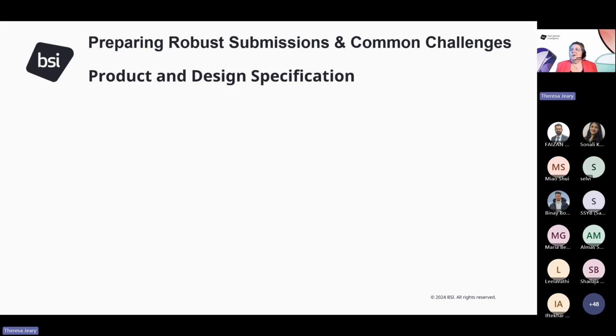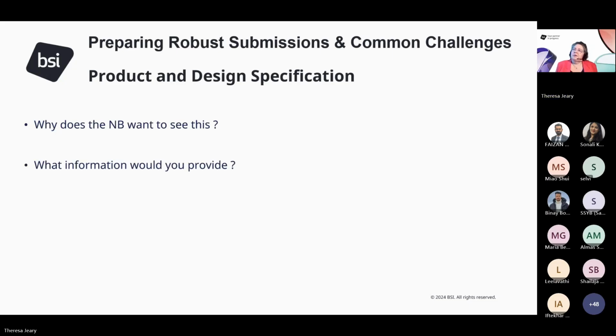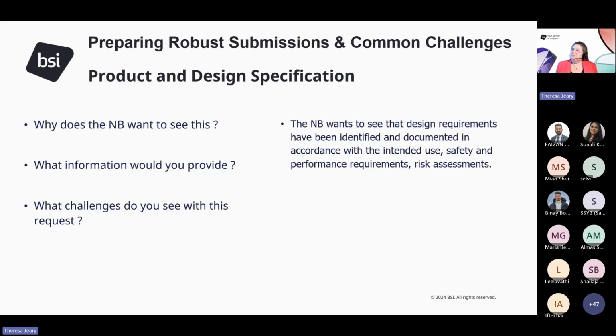Second on the list of common challenges were around product and design specifications. And again, wondering why on earth do you want to see this? It's a medicinal product. And think about it. What information would you provide in terms of this? And what challenges could exist here? For this one, the notified body wants to see that design requirements have been identified and documented in the intended use, safety and performance requirements and risk assessments. So your medicinal product, you've decided it needs to be delivered in a particular way, can be layperson use. All of that is part of that design, and you've gone through your risk assessments as well, thinking about that. So you've put a lot of thought and effort into what is this product going to look like, and what does this device need to be able to do to meet my overall product requirements.